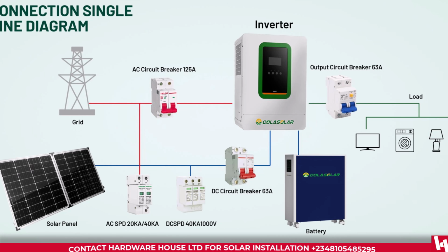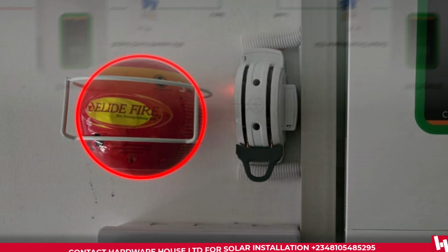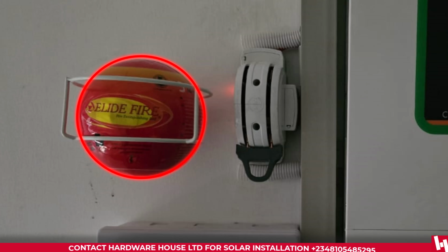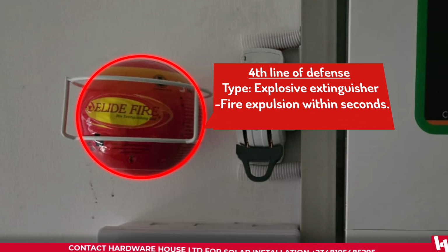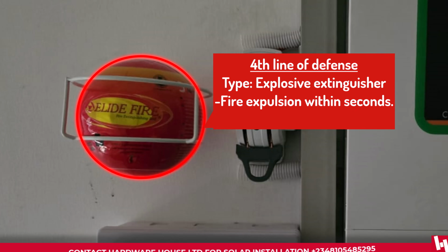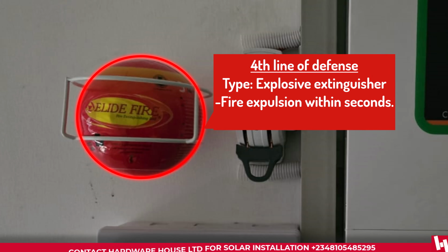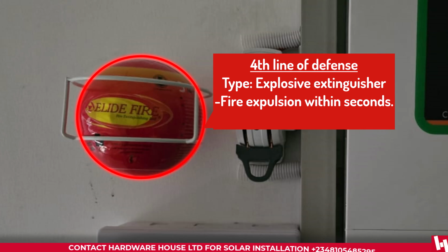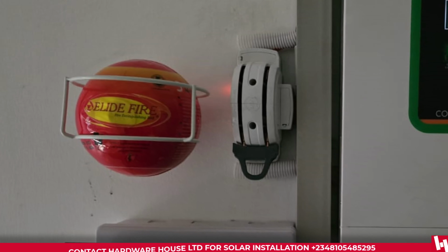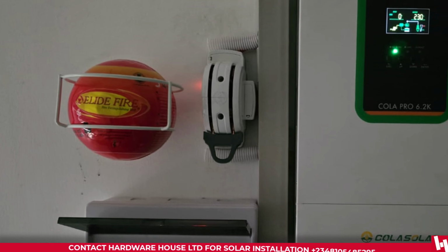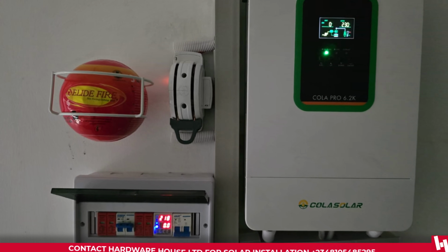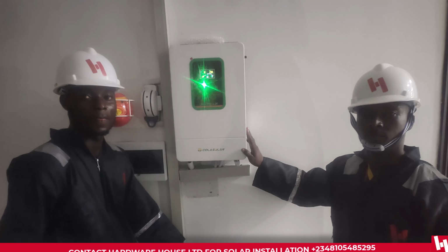And then the battery management system on the battery somehow fails, or anything goes wrong in this system and there is anything that looks like a fire outbreak. The fourth line of defense is the fireball. This fireball is packed with high pressure extinguishing fluid. That means if there is any form of heat, fire, or anything that looks or smells like fire, it's going to explode and extinguish that fire in a matter of seconds. So that is the fourth line of defense. These are the four different lines of defense that we have to make sure this setup is very safe from fire, safe from any form of failure.